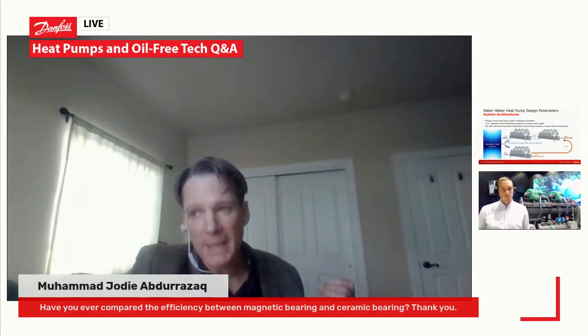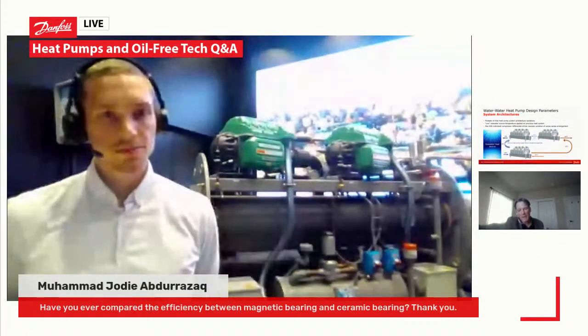I know that a magnetic bearing based system, in terms of losses associated with that bearing system, is more efficient than traditional steel, and I believe that corresponds also with ceramic. But if you look at it from a product standpoint, that comparison becomes most important. Ceramic bearing oil-free solutions are very efficient, but the ceramic bearing-based oil-free system also adds a lot of complication, because you have to lubricate that ceramic bearing-based system with liquid refrigerant as well.